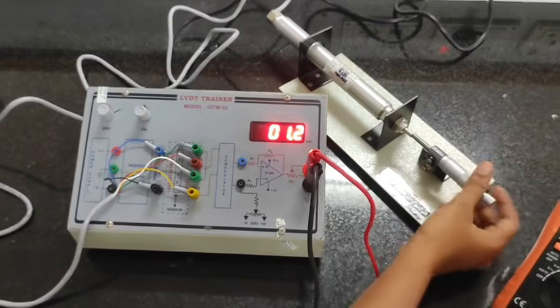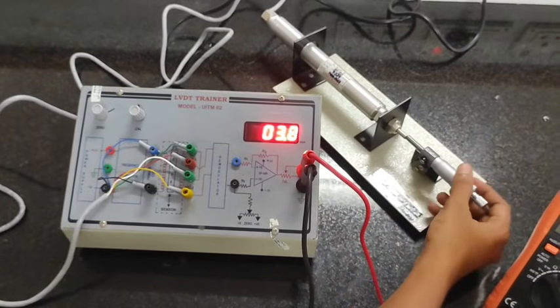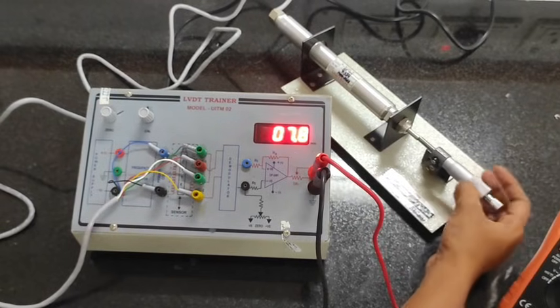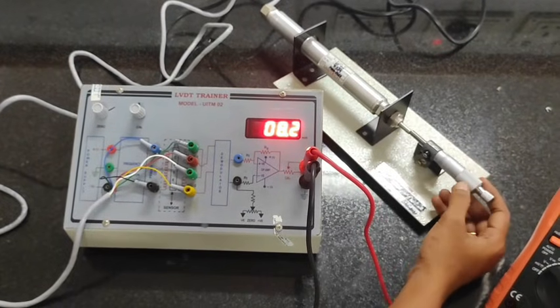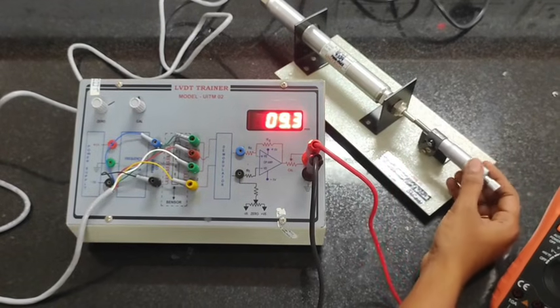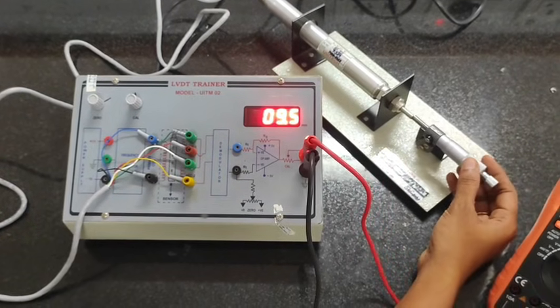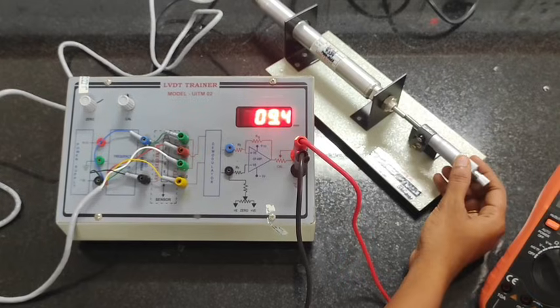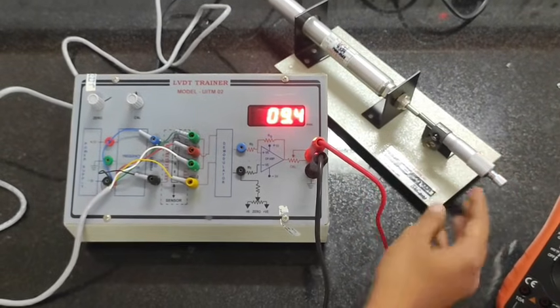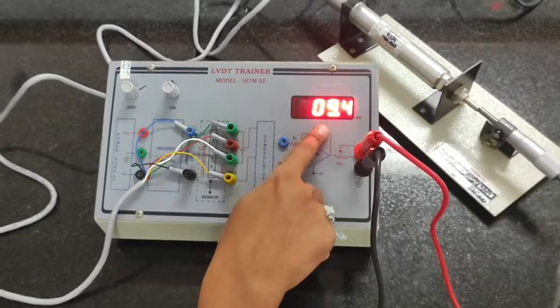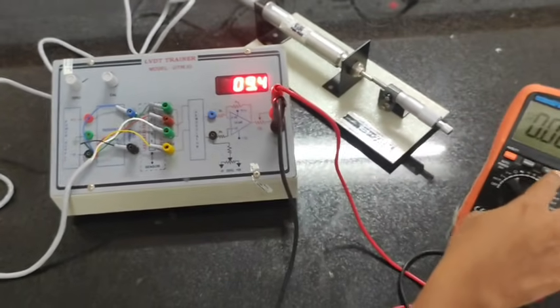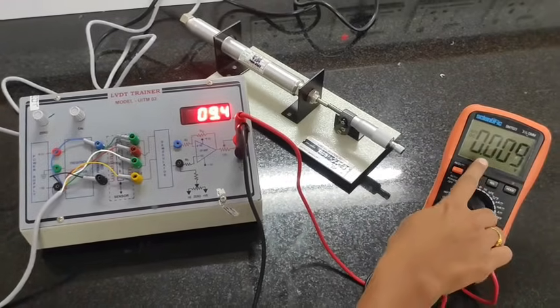Now I am increasing the value by moving this screw gauge, which moves my core position outward toward the red side. The scale value will be increasing, and in the displacement also it is observed - the value is increasing. For the maximum position, I have to check whether the displacement is increasing in a linear way and correspondingly whether the voltage is varying.